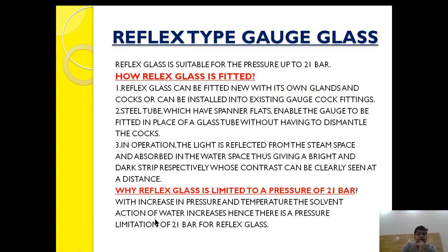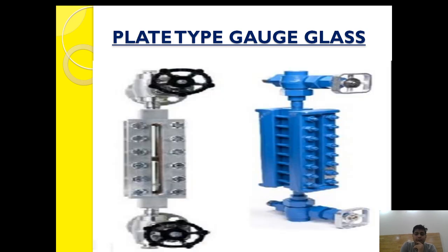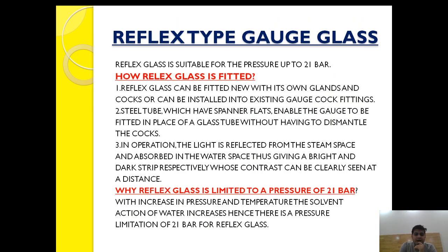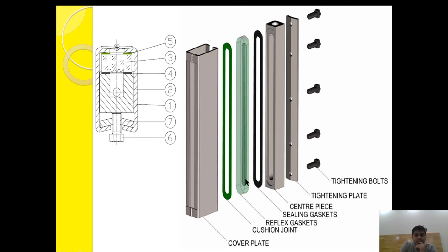The pressure range of the reflex type gauge glass is limited to 21 bar. This is because with increase in pressure and temperature, the solvent action of water on glass increases. In the plate type gauge glass, a mica strip is provided so that it can withstand the high temperature — as temperature increases, the solvent property of water to dissolve glass increases, and the mica strip counteracts this. However, since the mica strip bonding is not provided in the reflex type gauge glass, it is limited to a pressure of 21 bar.